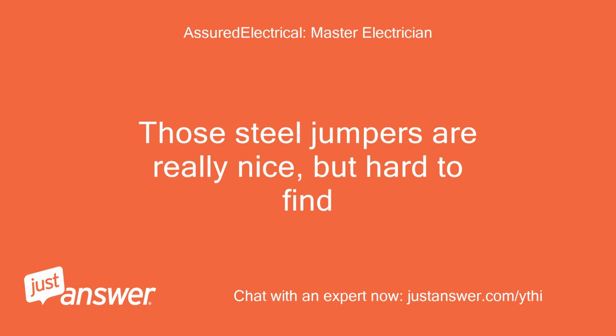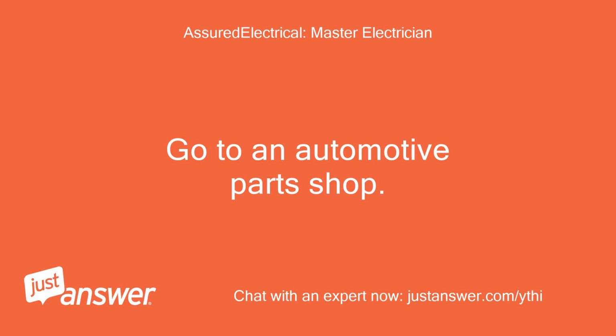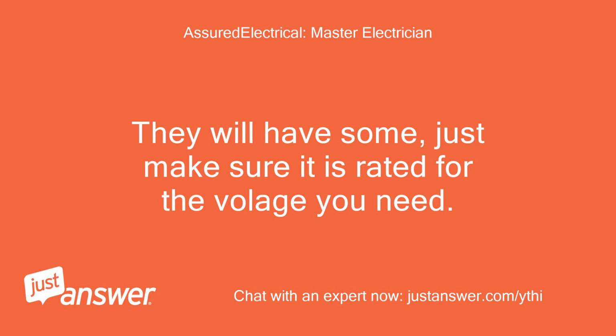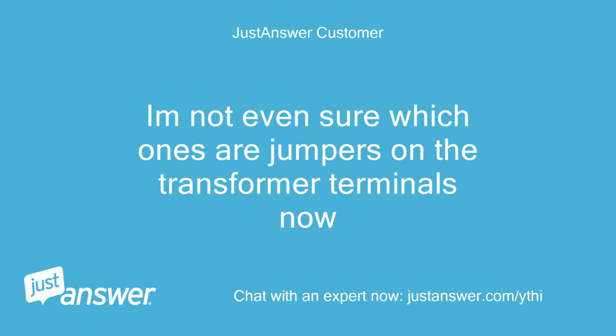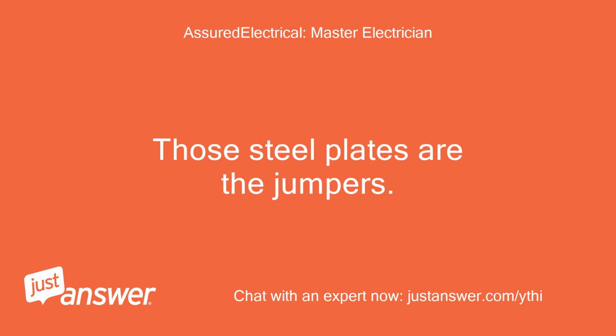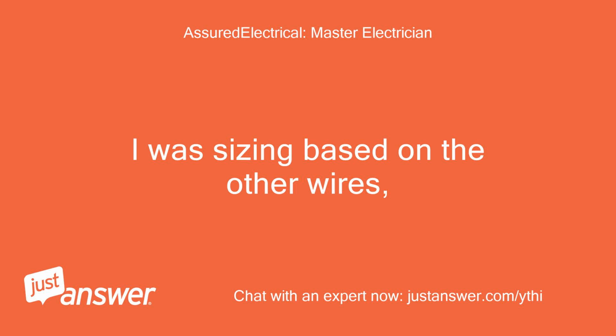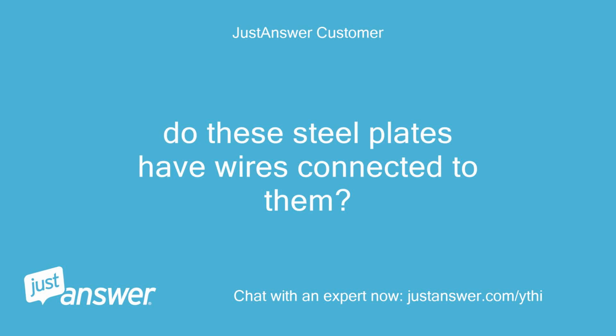Those steel jumpers are really nice, but hard to find. Go to an automotive parts shop. They will have some, just make sure it is rated for the voltage you need. I'm not even sure which ones are jumpers on the transformer terminals now. Those steel plates are the jumpers. I was sizing based on the other wires. Do these steel plates have wires connected to them?